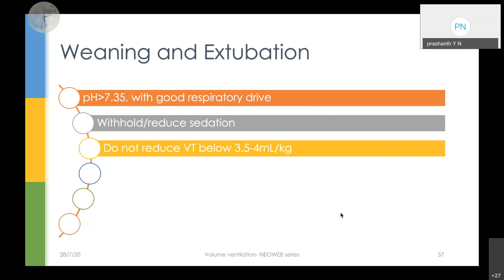We need to look at the pH, which should be more than 7.35 with a good respiratory drive, and we need to ensure that we have withheld the sedation, and probably some units would reduce the sedation volumes. And the other most important thing is, when we are weaning, we need to understand that volume guarantee itself is an automatic weaning mode. We need not look at decreasing the tidal volumes to wean it. So even if you have to decrease it, please don't decrease it beyond 3.5 to 4 ml per kg.